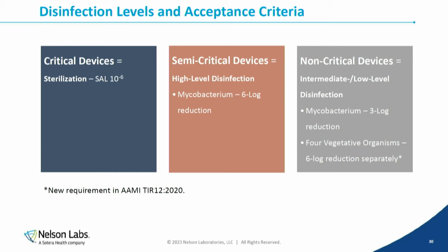Now, if you look at the acceptance criteria for all of these, look at this non-critical acceptance criteria. It's 6 log reduction of 4 organisms. You're not going to get that with label claims, okay? Your instructions for use should never say follow label claims.